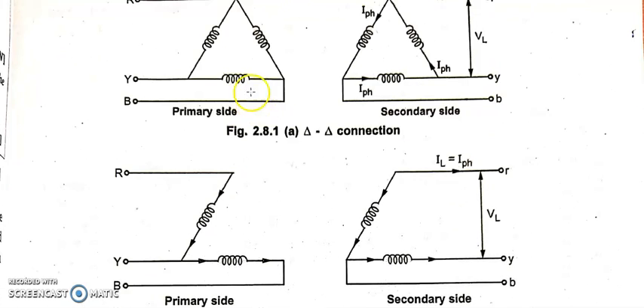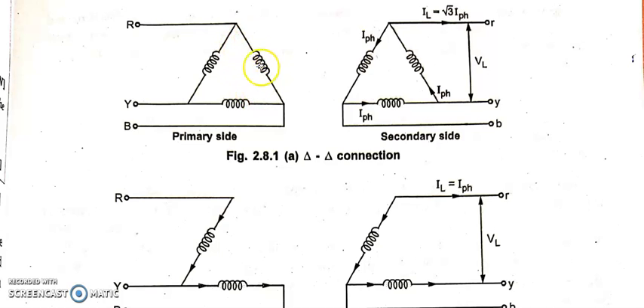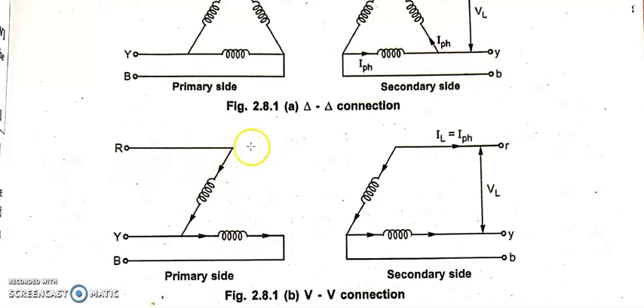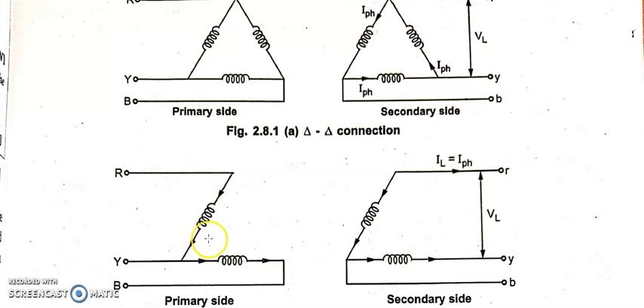Now coming to this, let us say this transformer has become faulty and I have removed it from the delta-delta connection, same with respect to primary as well as secondary. I have removed it. Yes or not? Even so, I can give three-phase supply to these two single-phase transformers, and I can take three-phase supply out of these two single-phase transformers, thus making a VV connection. So one thing remained the same here, that is, phase voltage and line voltage remained the same. But what about phase current and line current? Are they remaining the same here?